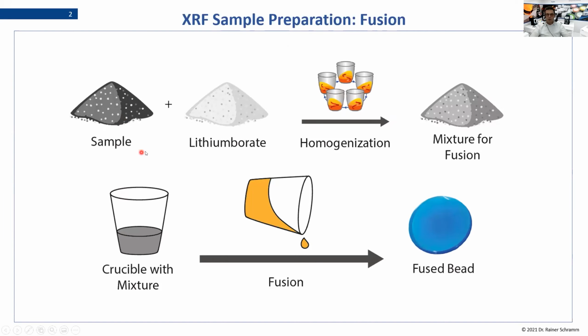Normally you use a dilution of 1:8 or 1:10 between your sample and your lithium borate, your glass former. Then you homogenize the whole thing. You make a homogeneous liquid by heating it up. Then you pour it into a mold so that in the end you get an ideal sample, a fused bead. That means your original sample material is dissolved into a glass, like you can compare it with dissolving a sample into a liquid.